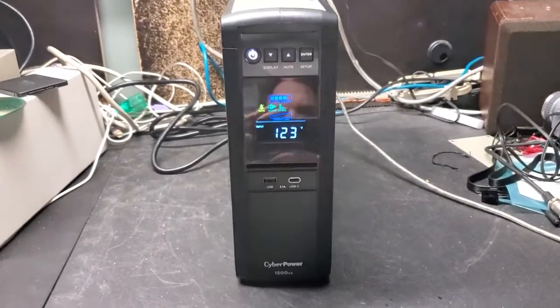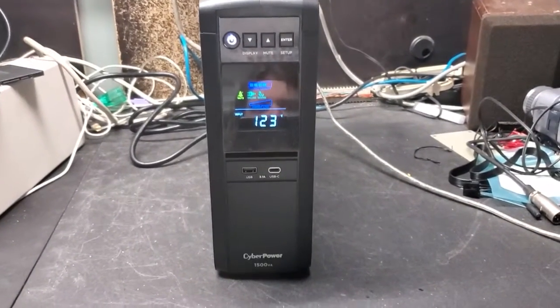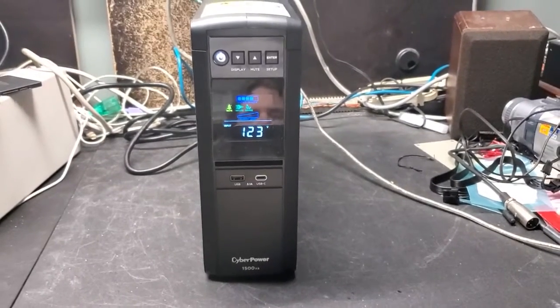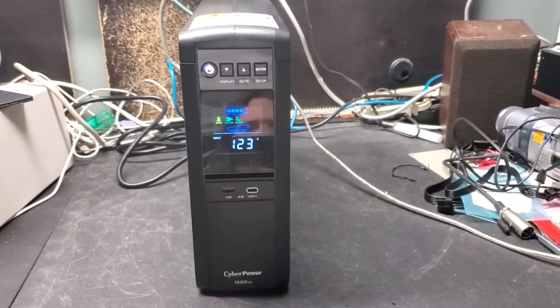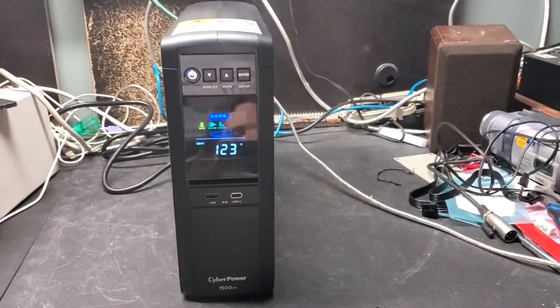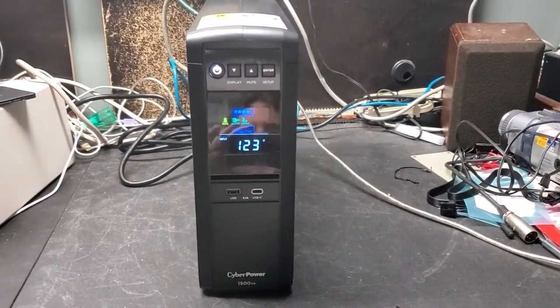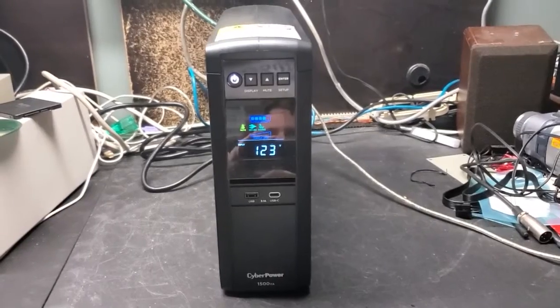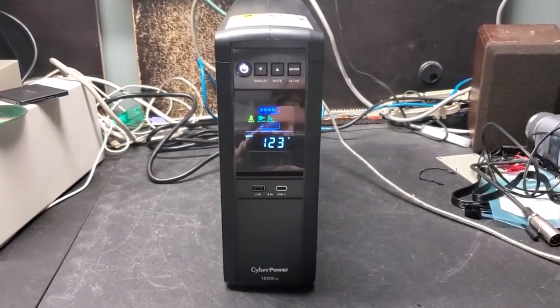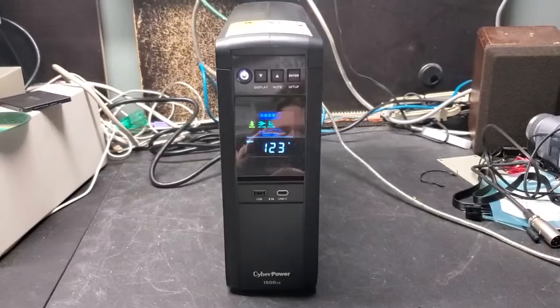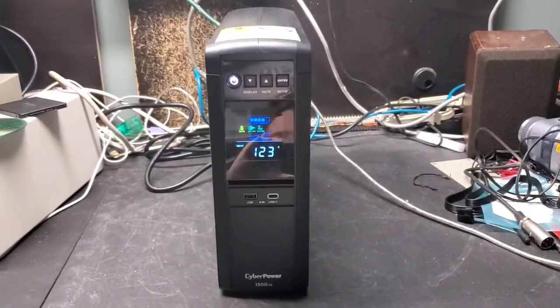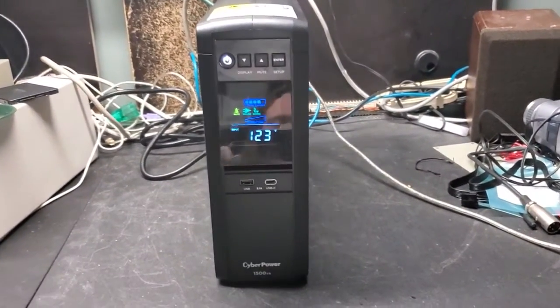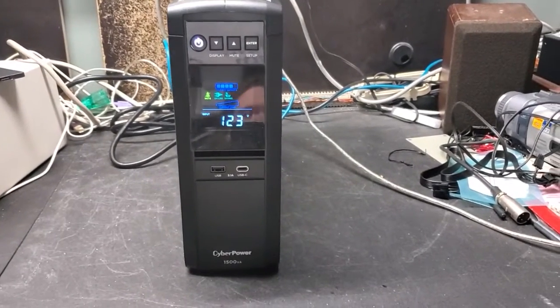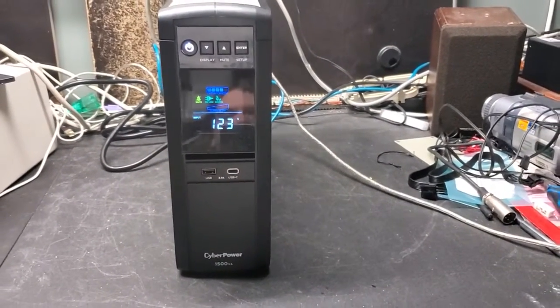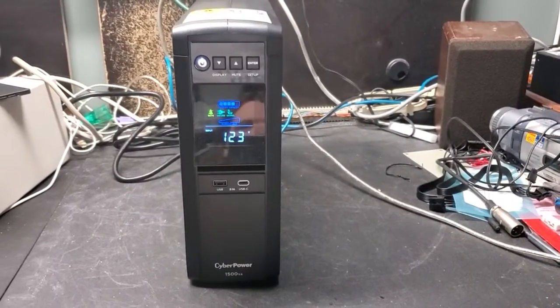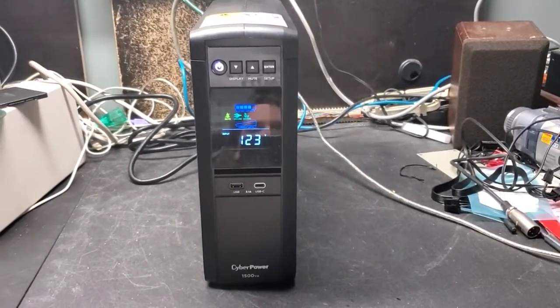So more affordable consumer-grade UPSs like this one are what's called a line interactive UPS, sometimes called a standby UPS. That means when mains power is present, the load connected to the UPS is being directly powered by the mains power. The UPS, the inverter, is bypassed and out of circuit, and the load is just being directly powered by the mains power.